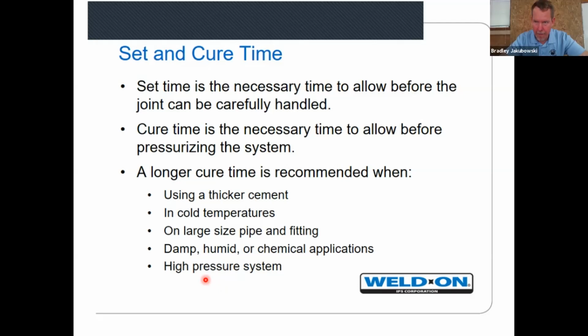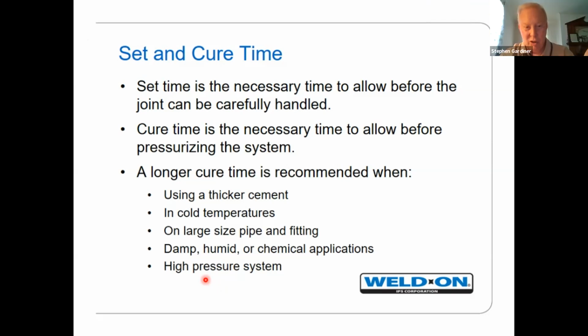You'll have a 6-inch length of 2-inch diameter PVC Sched 40 pipe and 2 Schedule 80 2-inch diameter caps to assemble. Okay. Normally on your job sites, you're testing at about 100 PSI, I'm assuming. These will get tested at 750 PSI, a whole lot higher pressure. So we're going to let them cure for 2 weeks. So I'm not testing your cure time. I'm testing your workmanship. Okay.